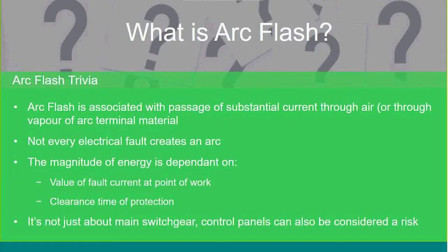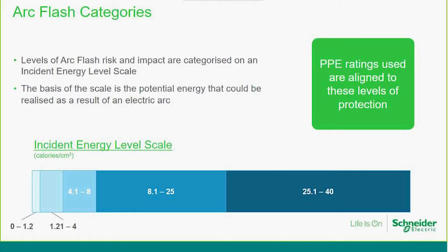But if you think about an industrial environment where you may have a control panel, that may just be an operative who one day is making cream eggs and is next asked to reset a piece of equipment in a control panel. There still could be an issue with incident energy levels and arc flash at that level. So it's not just about main heavy items of plant when we talk about arc flash.